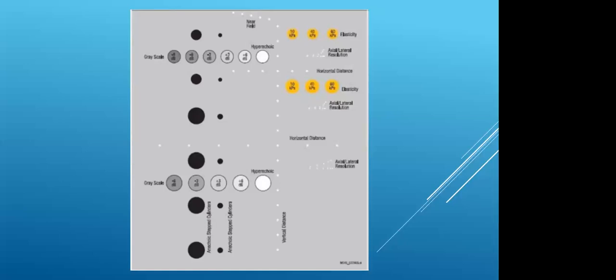And because these are different materials, as long as you can get somebody with a decent workshop, they could fabricate something with gels and different materials, and then you use that as your QA phantom instead of actually investing in a commercial one. Although I still argue that a commercial phantom is a requirement and should be part of the initial buying process, where you say, I'm going to buy my equipment, and that equipment should include the phantom. I think that is also traditional in most emerging sciences.